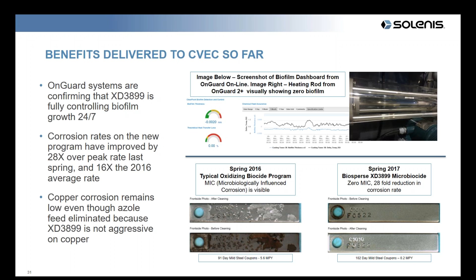So there's a number of benefits that we've realized here at CVEC. Previously, we relied primarily on close visual inspections of the equipment, often internal inspections of heat exchangers and plate and frame heat exchangers on the cooling water system when they were taken offline, relying on those inspections to check for biofilm. That was problematic, as Tim alluded to before. When you're talking about such a thin film that can impact the cooling efficiencies, it's hard to appreciate the impact that they might have.